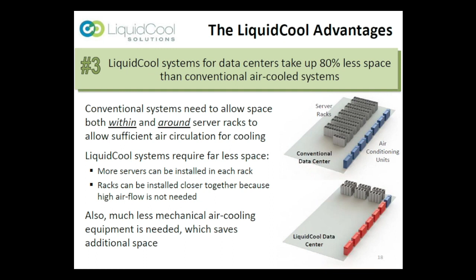And a fourth advantage, and this one might not be obvious, but it turns out that servers cooled with our immersion technology would be expected to be more reliable. The reason is that by immersing electronics in our heat transfer fluid, they're protected from many of the major causes of electronic failures. There's no exposure to air or any airborne contaminants. We don't have any mechanical parts like fans in the servers. Temperatures are kept more constant, they're kept lower. There's no vibration, there's no exposure to electrostatic discharge. And all of these are factors that plague conventional servers that we don't need to deal with. So servers potentially, because they fail less, because they can be used longer, can have a significant impact on reducing e-waste.